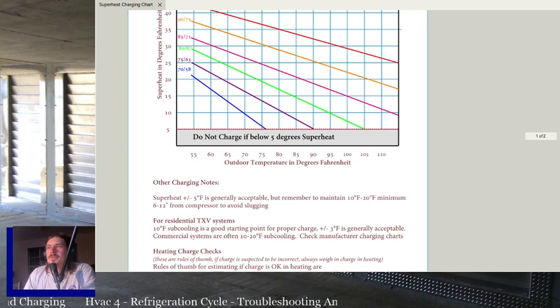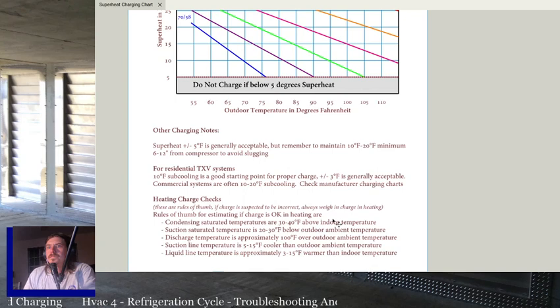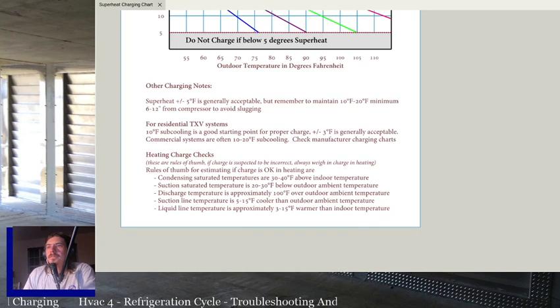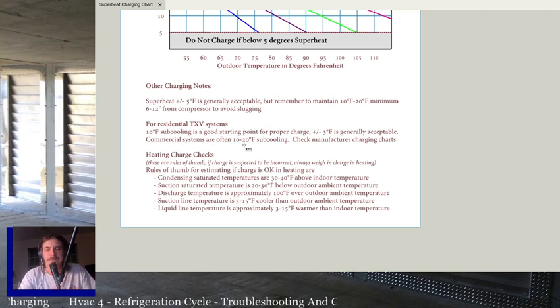I guess I can pull down some more. All right. Other charging notes. Superheat plus or minus 5 degrees is generally acceptable. With modern gauges and stuff, there's really no reason to not be as close as possible to what your target number should be. But plus or minus 5 on superheat is generally fine. That's kind of the range they'll generally give you and say it's okay. So plus or minus 5. If you're plus or minus 5 degrees on superheat and you think you need to charge, that's fine.